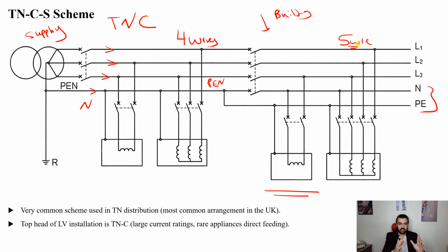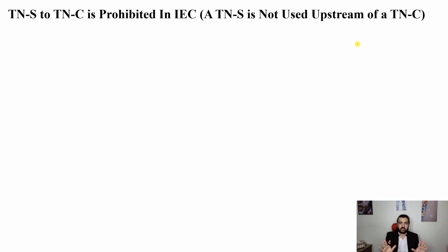So what we do is that during the distribution system, we start as TN-C in order to save conductors. Instead of having 5 wires, we only transmit 4 wires. And as we reach the load, we start converting into 5 wires in order to have the features of TN-S. Remember that in TN-S, I can use RCD, I can use circuit breaker, so there are many advantages of TN-S. So we started as TN-C to save an additional wire, then we separate them, as you can see here. Okay, so this is the commonly used.